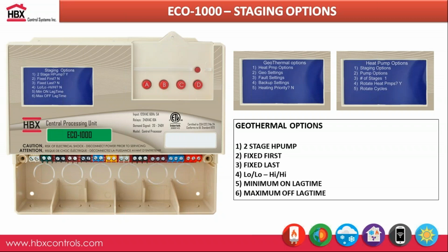You have options to, if you always want 1 heat pump to fire up first all the time, even if you're rotating your heat pumps based off lag time or cycles, you have that option as well. Or if you always want 1 heat pump to fire up last all the time, you have that option within the 1000 as well.